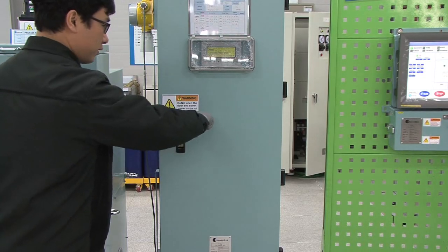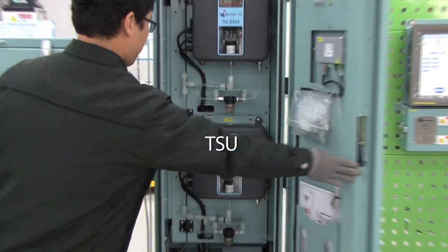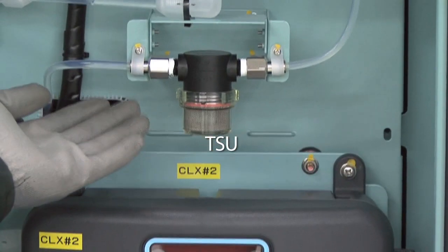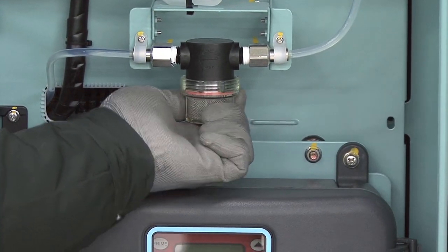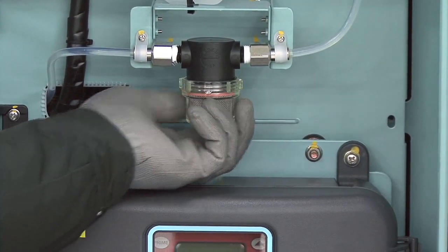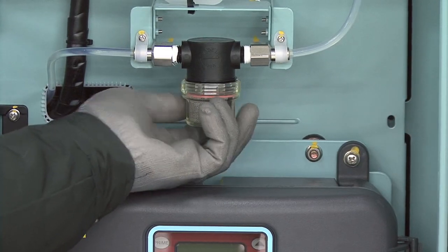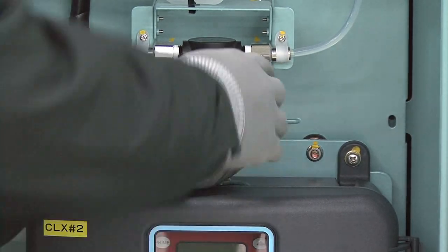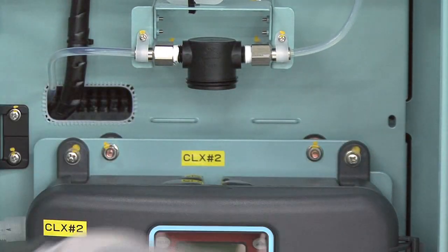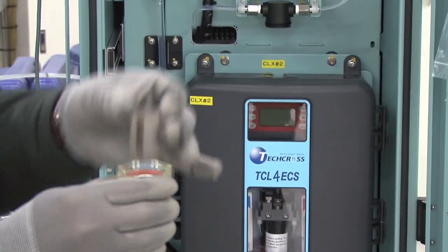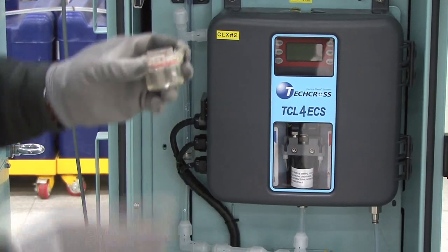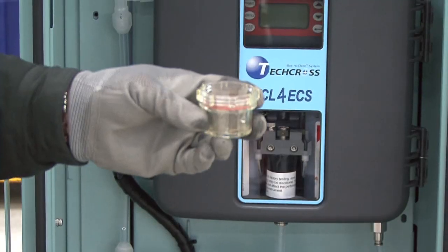Two. Regular maintenance. 1. TSU. 1-1. Cleaning CLX filter and check leakage. Step 1. Disassemble the quick filter by turning to the left. Step 2. Drain the water from the filter and clean it with compressed air, 4 to 7 kilograms per centimeter squared.